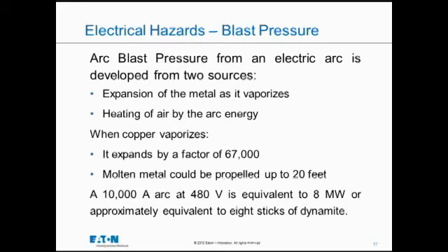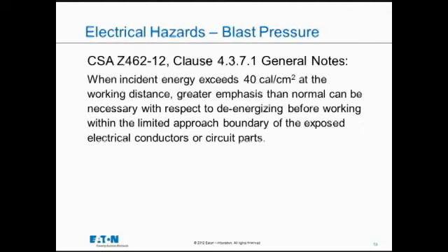So there is a concern as to when this blast pressure becomes harmful to the point that we're really worried about it. And in the Best Practice Guide, since the year 2000, they've created a line in the sand at 40 calories per centimeter squared. So when the calculations are done and the energy level at the working distance gets above 40 calories, then there should be something else done. And in this example here, taken right out of the Z462 standard, that's the exact words. It just says, do something different, something other than normal about this situation.